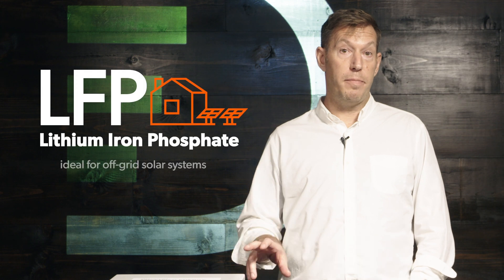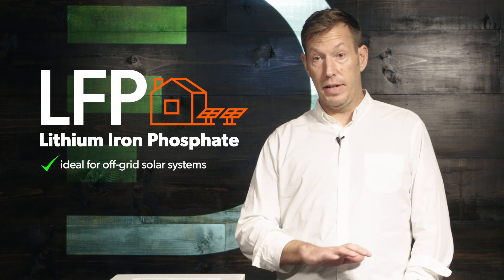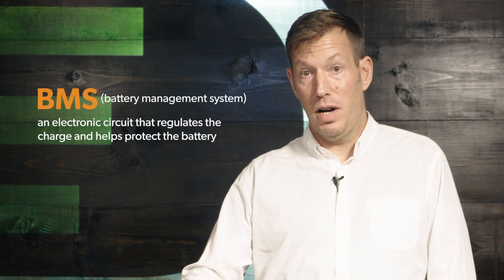A company that's going to build purpose-built batteries for solar applications is going to choose LFP — lithium ferrophosphate — as a chemistry every time. It's the least volatile of the lithium chemistries, which means it allows for very hard charging, very hard discharging, and the ability to handle a wide thermal environment. It's very stable — we've done destructive testing on these batteries: dead shorting and basically any abuse you can think of, and the worst case scenario is some discoloration and the BMS turns off. The cells themselves are incredibly stable. There are cylindrical cells, pouches, and prismatic as well, but the actual performance of the different configurations means nothing — battery specs are battery specs.